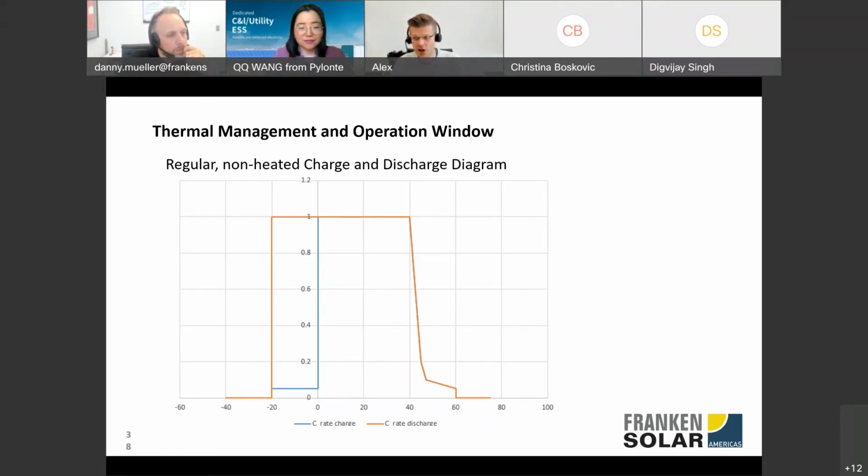And you can typically charge at full nameplate rating. In this case, it's about 100% of the charge rate. For the 12-volt batteries, that's 100 amps maximum, up to about 40 degrees. And if it goes beyond 40 degrees, then you should not charge at full power and should curtail the charge current a little bit, to not exceed the temperature ratings of that battery for proper life expectancy.